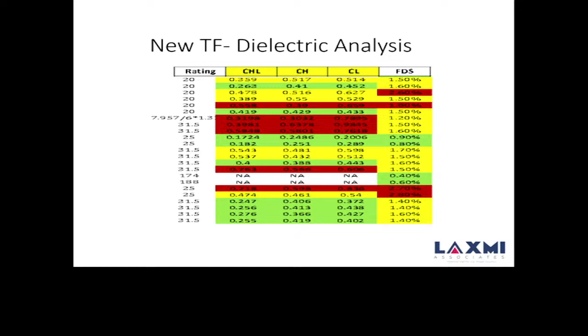So there is a case where everything is okay, the transformer looks good from outside, but we know that the moisture content is high, and it's a 2 to 3 years old transformer, not more than that. And at the last stage inspection, we find rusting in the transformer, and this is basically because the moisture content was high and it was giving such kind of problems.